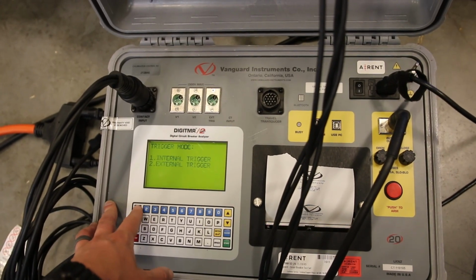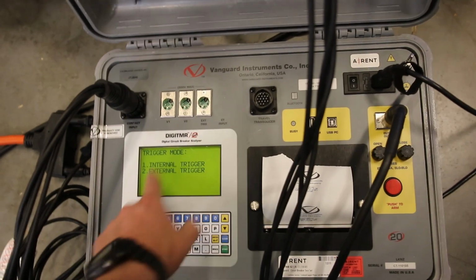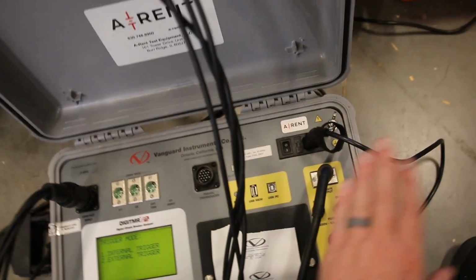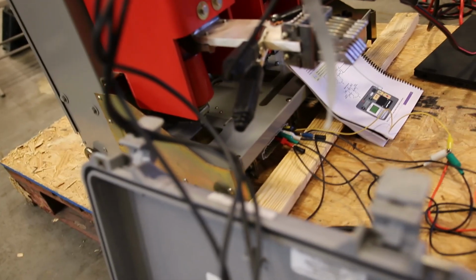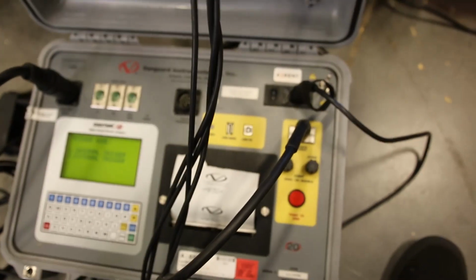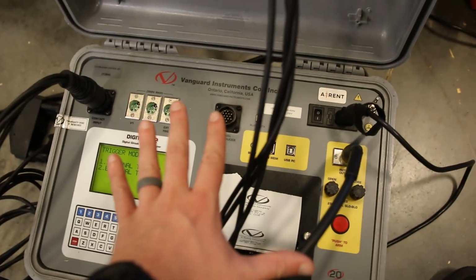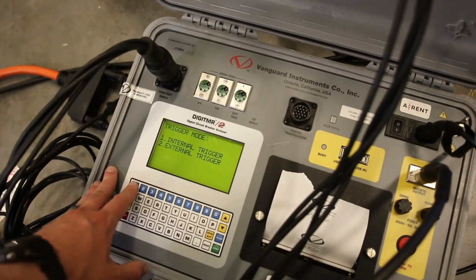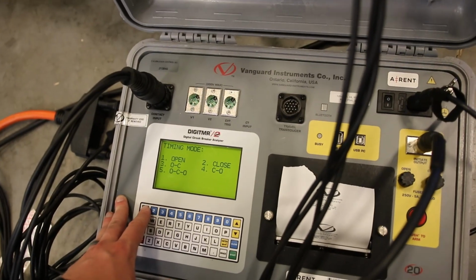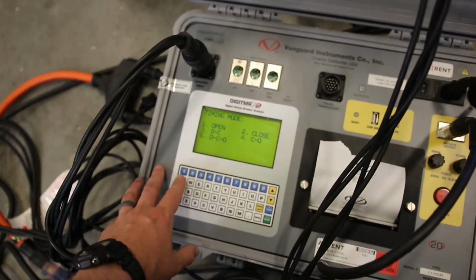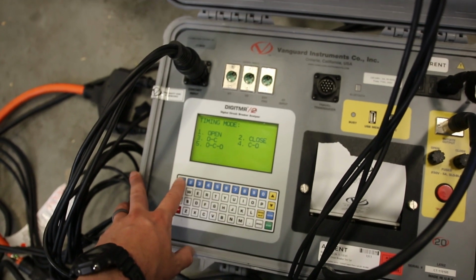Timing window, 1 second's fine, doesn't really matter. Internal trigger or external trigger. So I want my test set, these wires here that go to the aux block or the secondary contact block, I want the test set to control when it tells the breaker to open and close. So we're gonna go internal trigger, it's option 1. And we are open or closed right now. We're charged and closed. So we're gonna do the trip first, which is open, option 1.